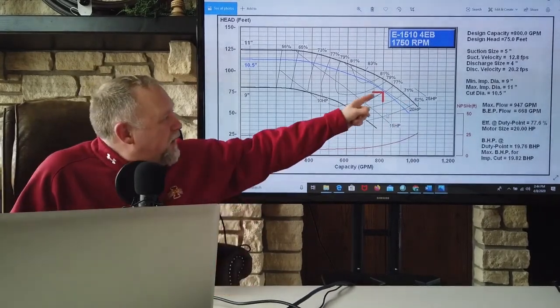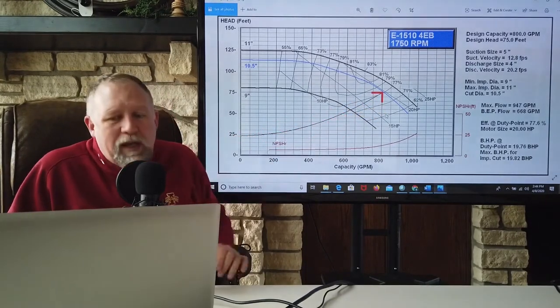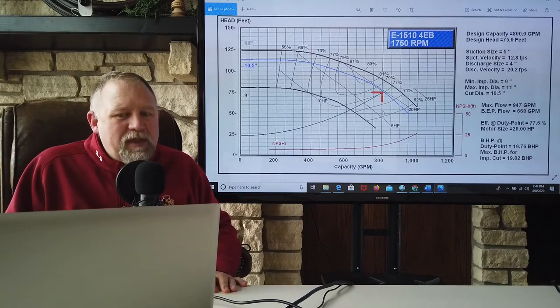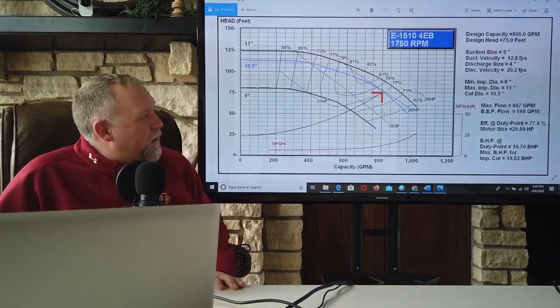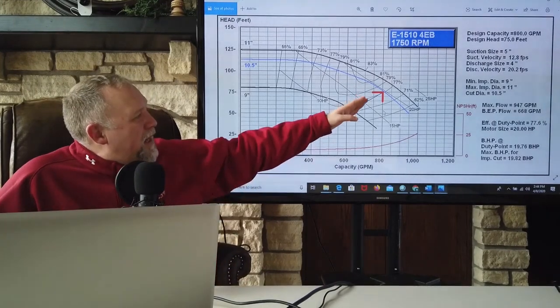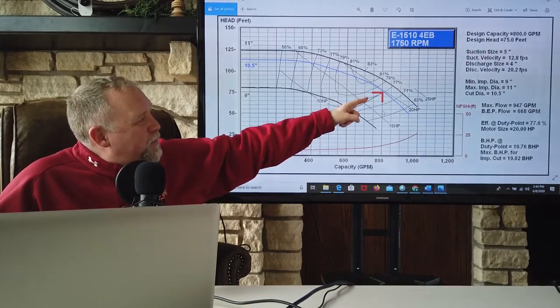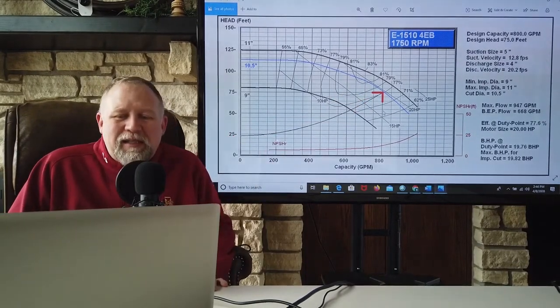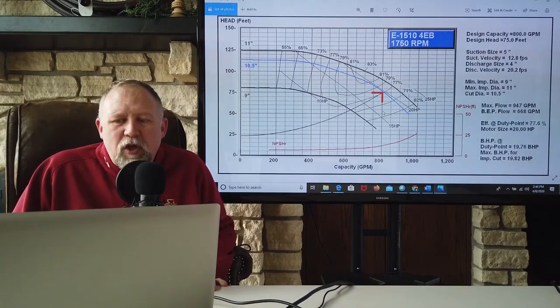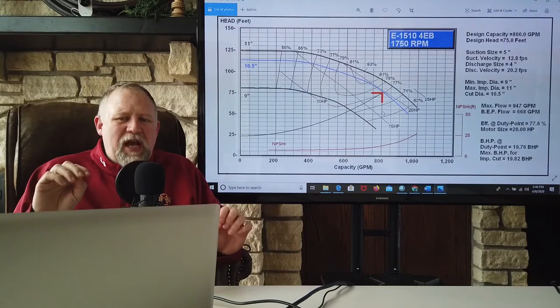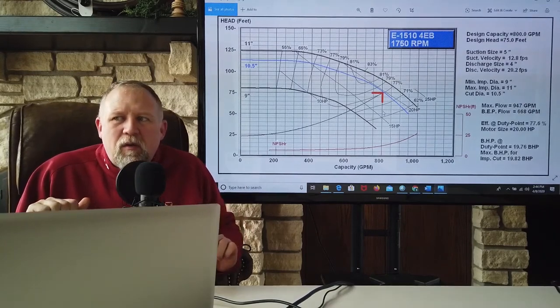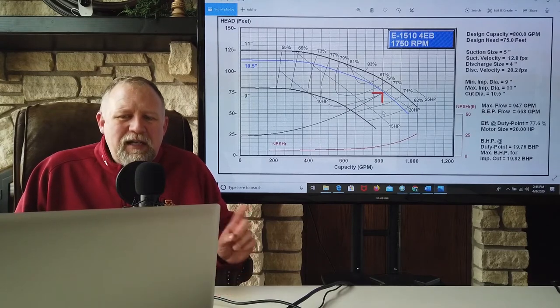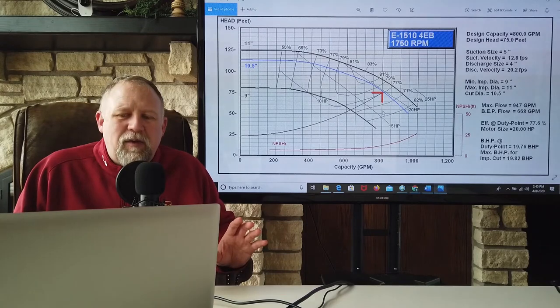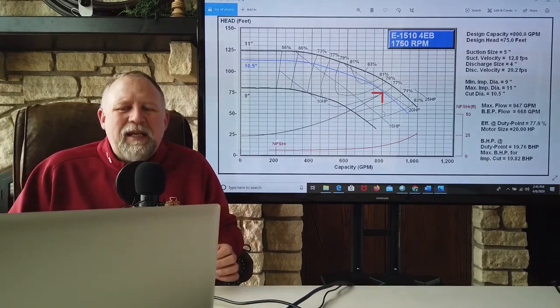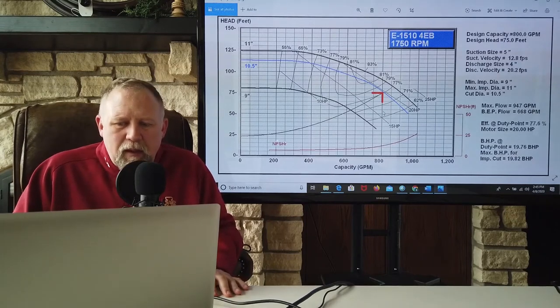Now notice here on this one how close that is to the 20 horsepower line. But the 20 horsepower line never crosses this particular impeller, right? What that means is no matter what combination of flow and pressure we're going to operate at, this pump won't overload this motor. And yes, that is actually possible. You could overload a motor. In other words, when you connect a motor to a shaft and you turn it on, motors are relatively simple electrical items. They are designed to operate at one speed. They're governed. That's all they know how to do. They're going to consume electricity until it operates at that speed, right?